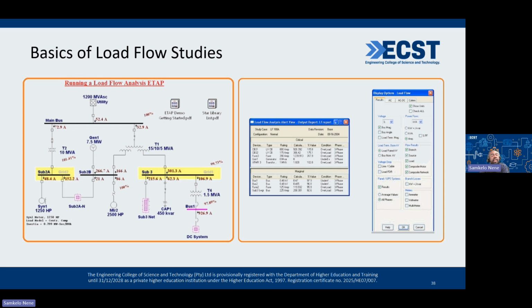This brings the aspects of grid codes. Voltage has to run at a certain percentage, power as well. With voltage, it shouldn't be less than 95%, not more than 105%. And with power, right above 90% of its nominal capacity. So when you design a power system, it's not just a matter of technical components, but there's also code that one has to abide by.